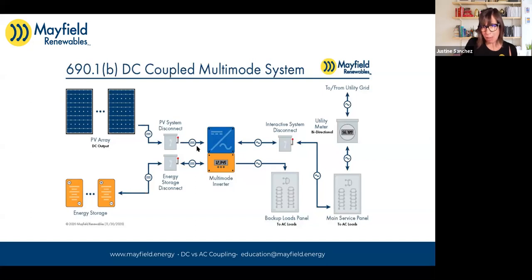A charge controller's job is basically to monitor the batteries, accepting power from the PV while the batteries need charge. As the batteries fill up, the charge controller watches the voltage level and the amps coming in and says they're getting a little full—let's taper off the PV, turn it down a bit because we don't want to overcharge the batteries, which would be bad for them and for us. So that charge control happens on the DC side. We can charge from the PV array to the energy storage, almost like its own DC bus with its own gear designed to work together at the right voltages, with no DC to AC conversion loss, because it's straight DC to DC on this side of the system.